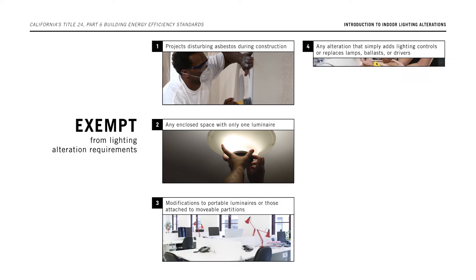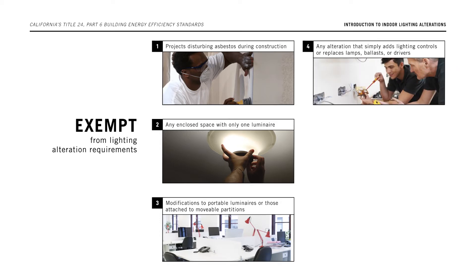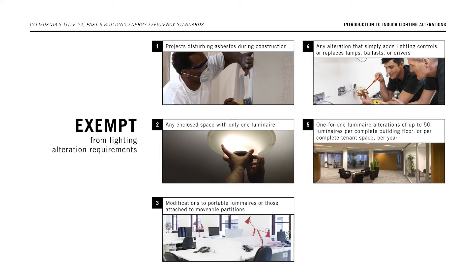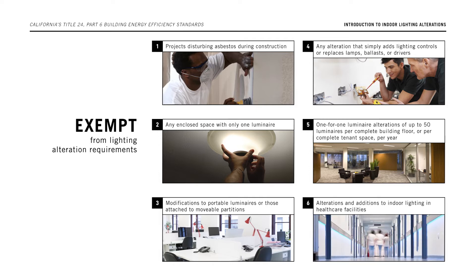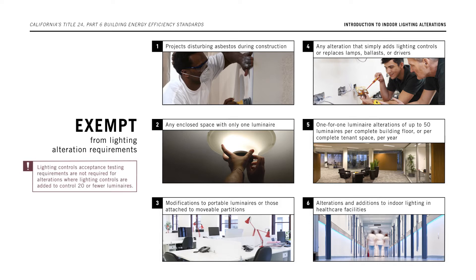Additional exemptions include any alteration that simply adds lighting controls or replaces lamps, ballasts, or drivers; one-for-one luminaire alterations of up to 50 luminaires per year per complete building floor or complete tenant space; and alterations and additions to indoor lighting in healthcare facilities. Also, acceptance testing requirements are not required for alterations where lighting controls are added to control 20 or fewer luminaires.